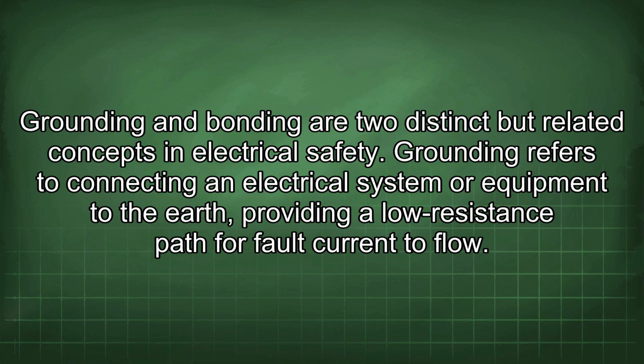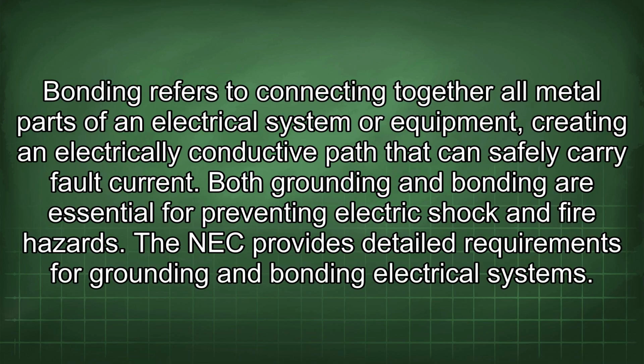Grounding and bonding are two distinct but related concepts in electrical safety. Grounding refers to connecting an electrical system or equipment to the earth, providing a low resistance path for fault current to flow. Bonding refers to connecting together all metal parts of an electrical system or equipment, creating an electrically conductive path that can safely carry fault current.